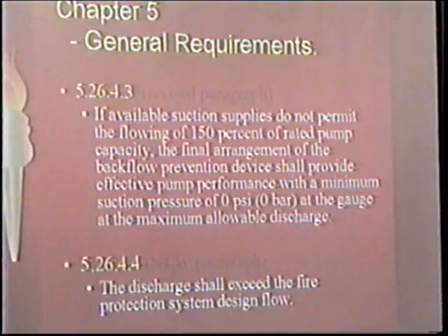Because right below that, it goes on to say, exceed the system design. Yeah, that the discharge shall exceed the fire protection system design as well. There's always been a little bit of an unclear issue in the past: the code stated that if a fire pump did not flow 150% of the rated capacity of the pump, it does not constitute a failed acceptance test. It was kind of a negative way to say it. It didn't say it passed, it just said it didn't fail. I think this is part of that, and a little later on, I don't know if we have that slide or not, but they did change that wording to say that it is acceptable.